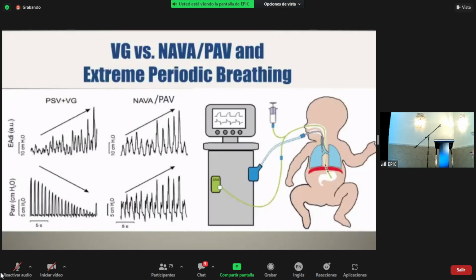All right, so I'm going to draw the contrast between NAVA, which I briefly talked about in the previous talk, and volume targeted ventilation. So if you measure the electrical activity of the diaphragm with this NAVA catheter, you can do that with NAVA. And in Europe, they have something called proportional assist ventilation, which is a very similar concept. And they're both positive feedback. So when there is little effort generated by the baby, there's not much pressure delivered by the ventilator, because it is assumed that the baby knows what they're doing. And when the baby breathes more vigorously, more pressure is generated.